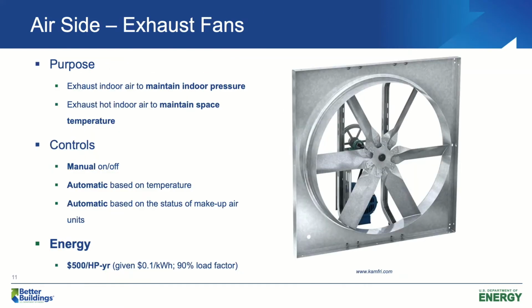Exhaust fans. All right, we take a lot of outdoor air into our spaces, either through air handling units or makeup air units. We need to exhaust some air out. Otherwise, our buildings will be overpressurized and we might have some problems closing our doors or windows. Sometimes we also use exhaust fans to maintain space temperature. For example, for some mechanical rooms, we typically do not have air handling units to directly deliver cool air to our mechanical rooms. Instead, what we do is that we exhaust the hot air out. Hopefully we can get some cool air from the adjacent spaces.